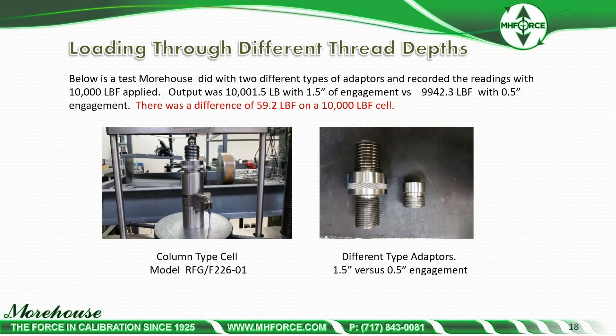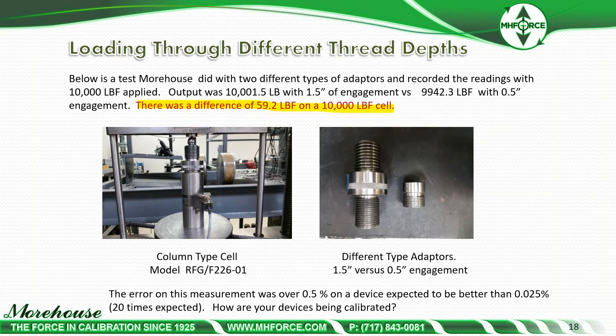Thread depth is another consideration. We ran a test using two different size adapters — one with one-and-a-half-inch engagement and another with a half-inch engagement — and the output varied by 59.2 pounds at 10,000 pounds. The error of the measurement was over half a percent on a device expected to be better than 0.025% at full scale — 20 times the expected error. This raises the question: if you're sending devices in to your calibration service provider without adapters, what are they doing? Right here you could have a half percent or more error.